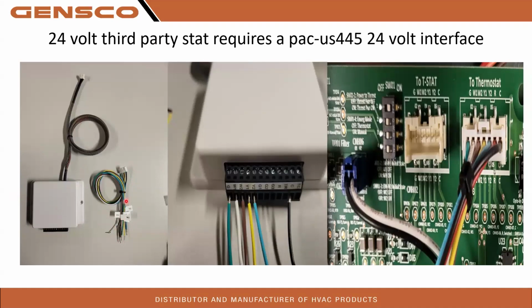This application, it does. So this pigtail, well, first off, the wire on this is for your CN105 connector on the control board. So that'll plug into CN105. This pigtail will wire up to your screw terminals right here, as you can see. And then this pigtail on the relay board plugs into this connector right here. It says To T-Stat, also known as CNH02. So your thermostat does not wire into this thing. I get guys making that mistake. The furnace isn't working because it's not ran through the relay board. It's communicating directly with the furnace. So the pigtail to the 445 plugs into the relay board right here.